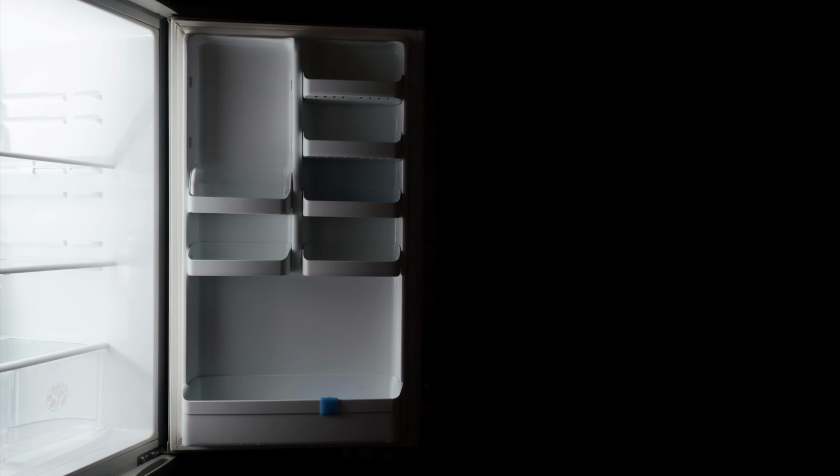Avoid overstocking them. This restricts the airflow within the cabinet, causing the cooling equipment to work harder and demand more energy. Make sure that any lighting and anti-condensation heaters are turned off at night or when not required. Automating some maintenance cycles can lead to better energy performance. Check the defrost settings and anti-sweat heaters to ensure that they are set up appropriately.